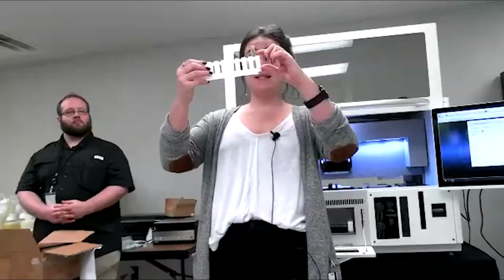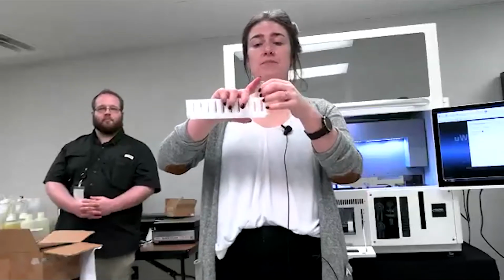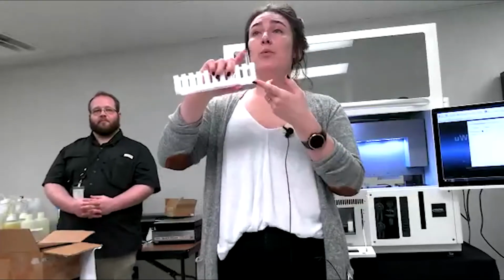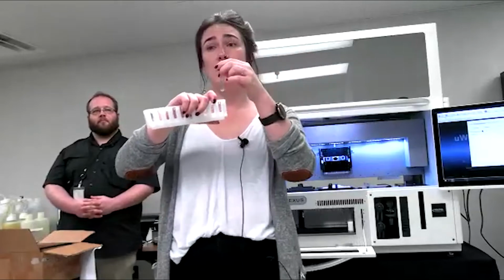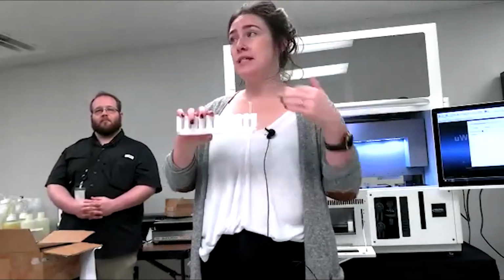But if your tube is, Dominic? Oh, sorry, go ahead. If the remaining sample is not enough for the rack, will the instrument continue to work? Yes, so if it doesn't find enough sample, it will go to the very bottom of the tube and aspirate anyway, and then dispense that into the sample. It will get everything that it can and proceed with the run. But in the run log, you'll be able to see it'll say insufficient volume. So that record will be there that there wasn't enough, but it's going to at least try anyway. It's going to get the most out of the amount of sample that you have.